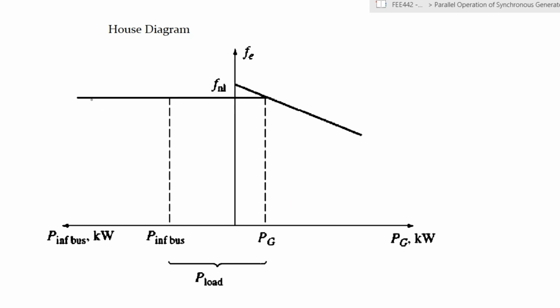For the infinite bus bar, whatever power is there, frequency will remain the same at this value. But for your single generator, remember it has the governor droop characteristic, so it will vary along that line. So in the case of a generator which you would like to connect to an infinite bus bar, that's what we talked about, synchronization. You have to alter the characteristics of the incoming generator to match the already existing infinite bus bar.